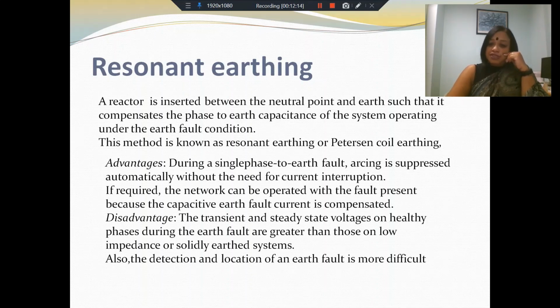Also, there can be steady state voltages on healthy phases during earth faults. If the earth fault is very high, then it might affect the overvoltage that you are likely to see, the transient as well as the steady state overvoltage that can appear on the healthy phases when one particular phase sees a fault. And therefore, in this kind of scenario, a solidly earthed system might be preferable. And the other problem with resonant earthing is, just as you can continue to operate the system under fault conditions, the detection and location of earth faults becomes more difficult.